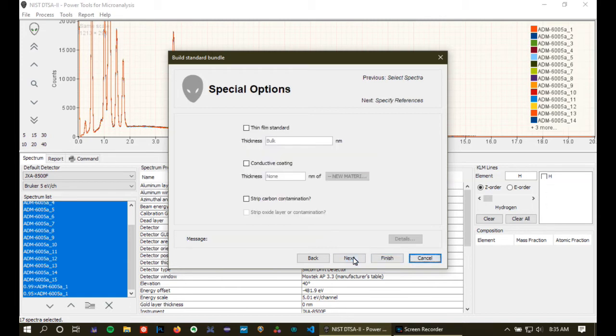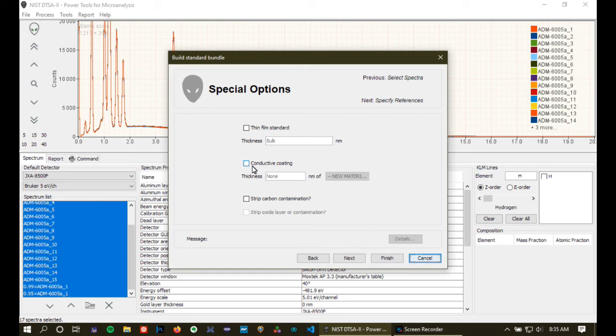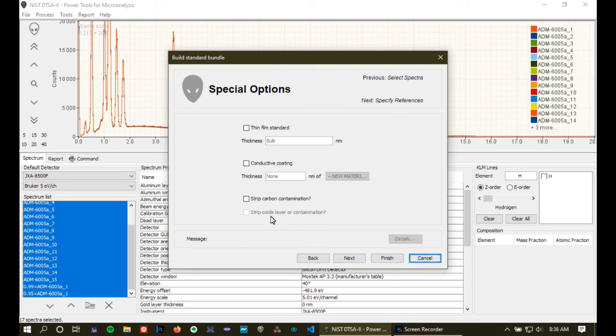Okay, then we get some options here. If you're using this standard, if it was collected from an unsupported thin film, and it's being used for the zeta factor method, then you can select this thin film standard. If you want to specify that there's been a conductive coating on the material, you can do that here, and then it'll ask you for a reference for that material. So if I were to select this and put a layer of carbon on here, it would ask me for a carbon reference. And there's also an option, independent of that, to strip the carbon contamination off. Or in the case that this material didn't contain native oxygen, then you also could strip the oxygen content off, too.